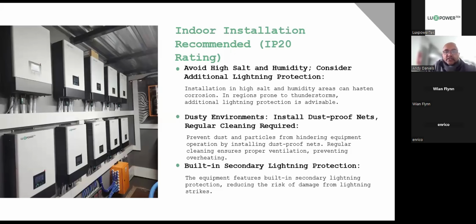Consider additional lightning protection. We're going to get into that in a second, but I want to focus more on installation in high salt and humidity areas. It's going to speed up the corrosion. We see it on the fan plate. Even though the fan plate is galvanized steel, we still pick it up on there, and also inside on the PVC shrouds that guide the fan air through the machine. We also pick up a lot of condensation inside those machines, and obviously that mixes with the dust particles that come through, and it forms a constant moist environment, and it's not good. I can show you some horror stories of what machines look like when they come back from areas like that. So make sure that you avoid these areas.